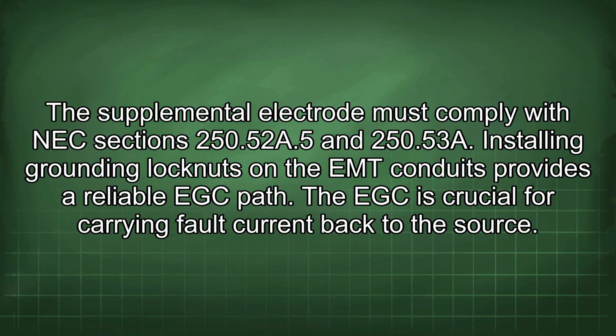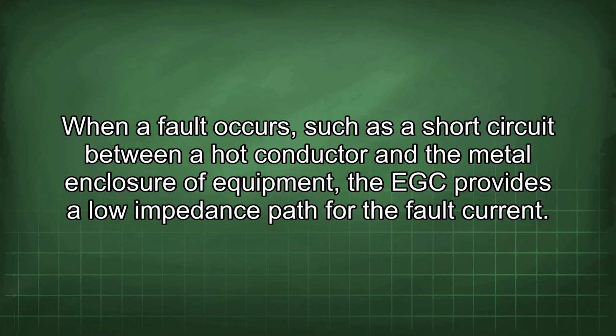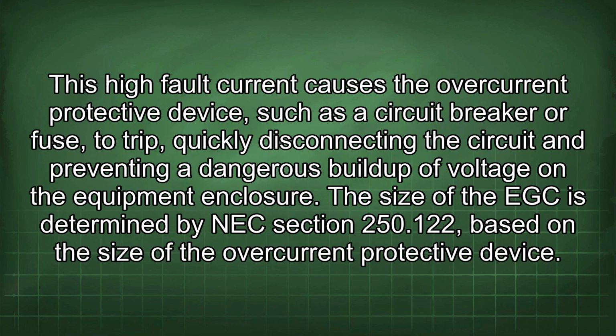The EGC is crucial for carrying fault current back to the source. When a fault occurs, such as a short circuit between a hot conductor and the metal enclosure of equipment, the EGC provides a low impedance path for the fault current. This high fault current causes the overcurrent protective device, such as a circuit breaker or fuse, to trip, quickly disconnecting the circuit and preventing a dangerous buildup of voltage on the equipment enclosure.